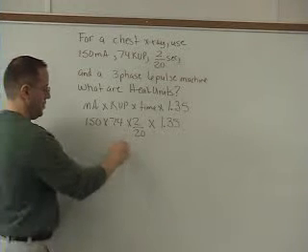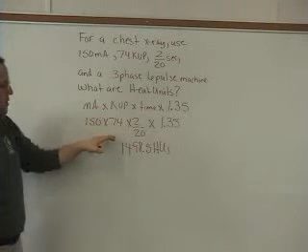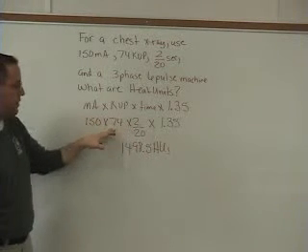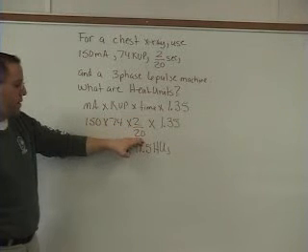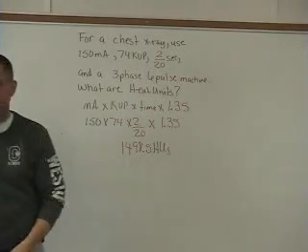So the answer would be 1498.5 heat units. Just remember, when you're doing the fractions, do the 3 top numbers, the 150 times 74 times 2, and then divide by 20. And then that answer times 1.35.